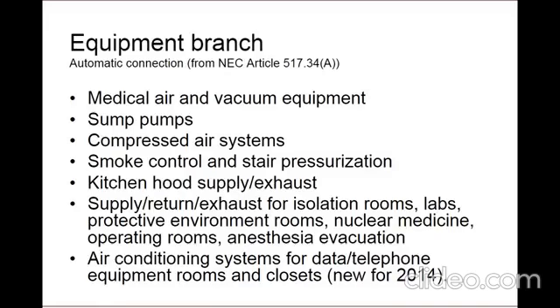And brand new for the 2014 NEC, it now also requires AC systems for data and telephone equipment rooms and closets. So this is important to note because it could affect that mechanical design. If the mechanical engineer is designing those rooms to be served just off of the VAV boxes, off of a regular old chilled water air handler unit, you better have a chiller on emergency power.